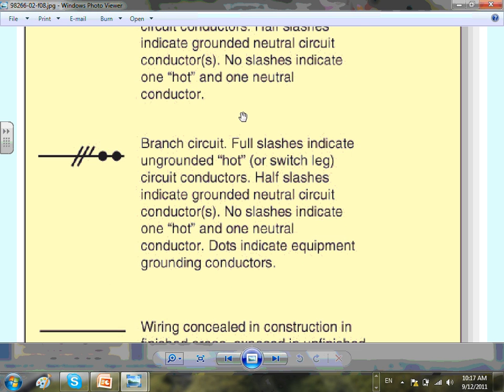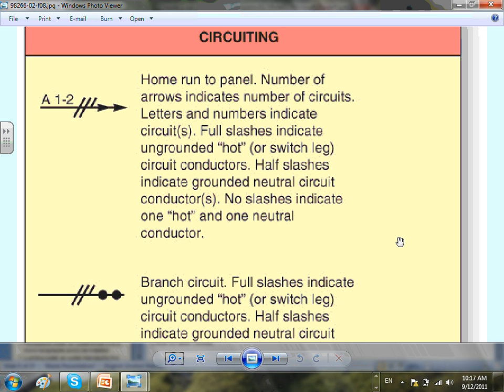If you look right here, it says hot home run to panel. Number of arrows indicates number of circuits. So how many circuits do I have here based on the arrows? Two. Not every firm uses this, guys - not every firm uses that one. So this is just theirs. For circuits, letters and numbers indicate circuits - so A1-2, that's circuit 1 and 2.